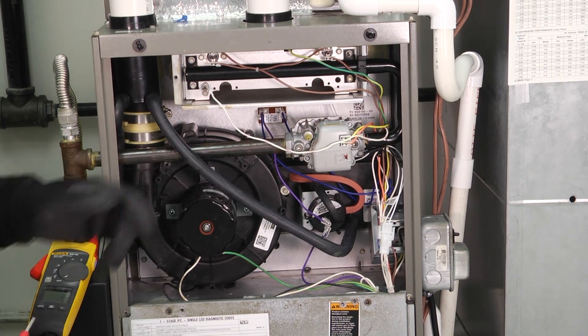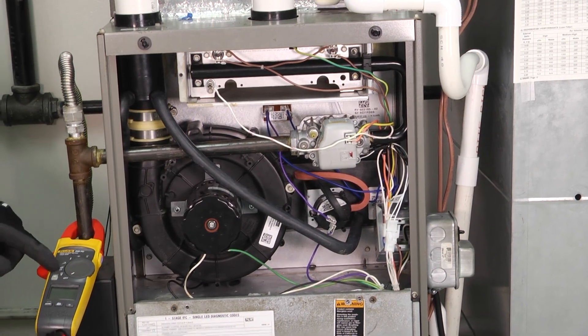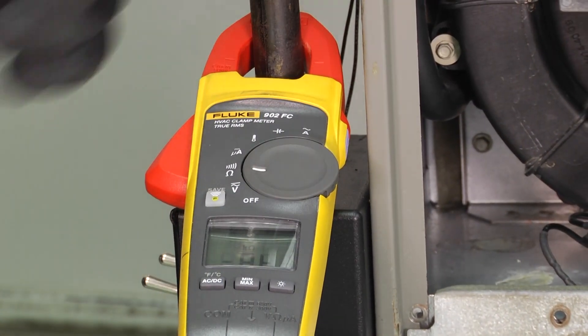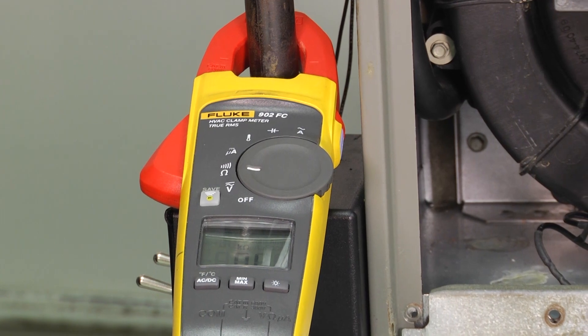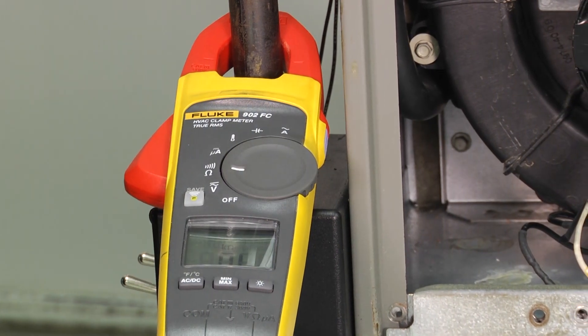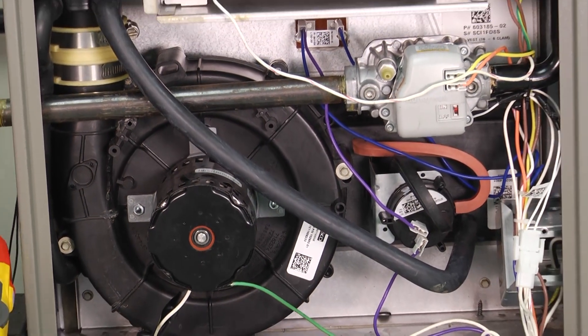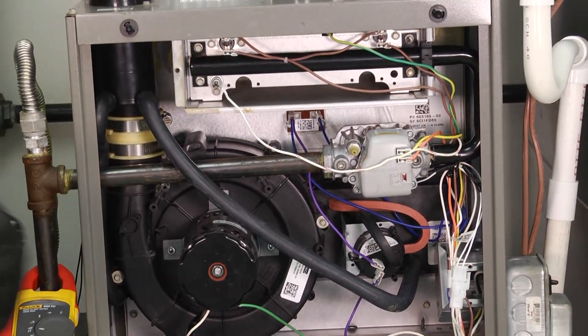So the very first thing, we have our meter. We're going to set our meter to ohms. Make sure that your system is de-energized, that it's not on. If you can happen to get to the hot surface igniter and the furnace has not been running, you can check it cold. That's going to give you the most accurate reading.